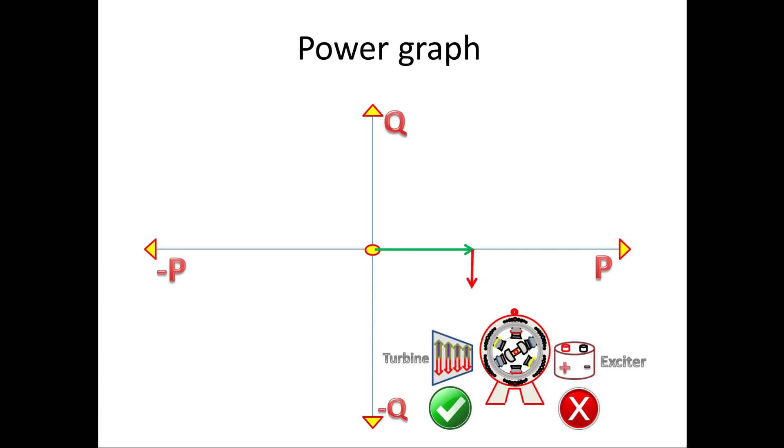The working of rotor is to produce strong magnetic field. Since the exciter is not delivering power to rotor, it has to take power from grid. Due to this, the VAR will be minus. That is, it absorbs VAR from the grid. So P is positive and Q is minus. This case comes under fourth quadrant.